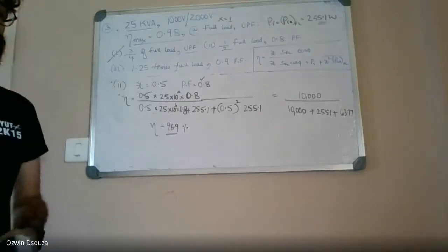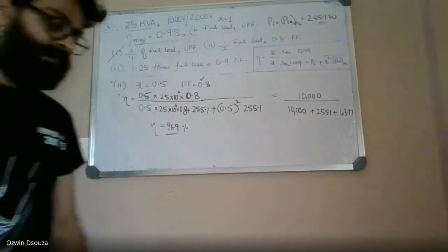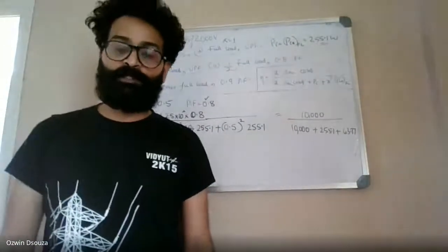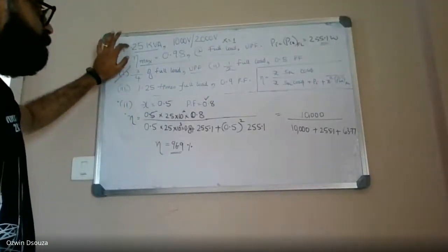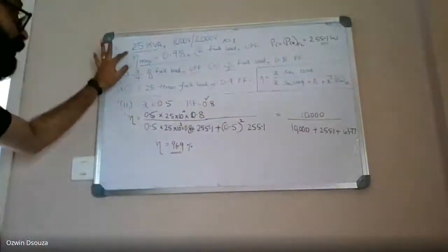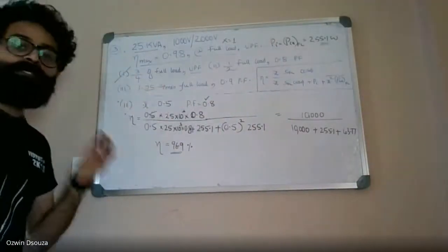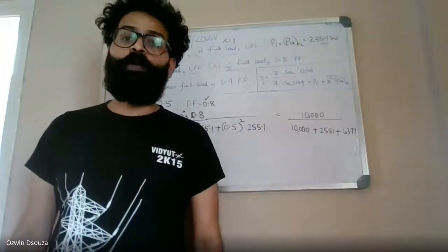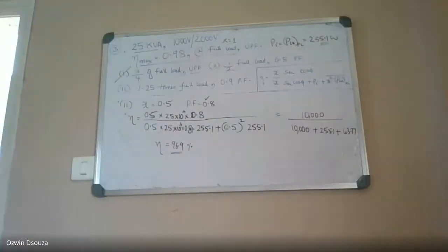And in developing countries, due to this overloading, you can observe this voltage fluctuation. You must have encountered the low voltage issues, right? So this low voltage issue is due to this reason as well. There are multiple reasons, this being one of the reasons, that is loading the transformer beyond its rated value. That is one of the reasons for low voltage issues, especially in developing countries.